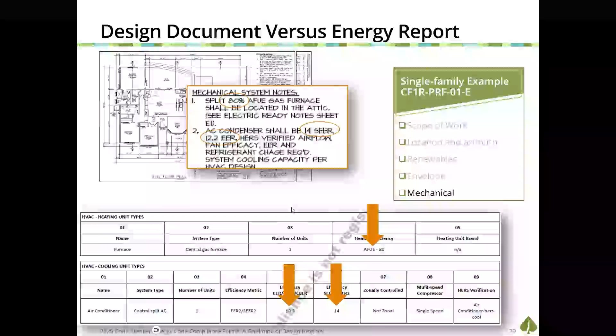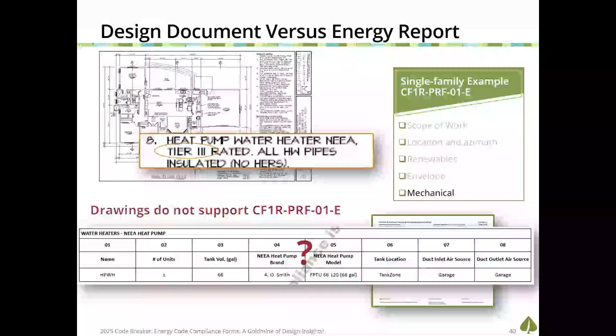Do you have the specs that show the mechanical equipment type, size, and efficiency fully supported within your design documents? Water heaters are specific now. For a heat pump water heater, I need the make and model number. It's not generic, it's specific. And I need that to be supported in your design documents.